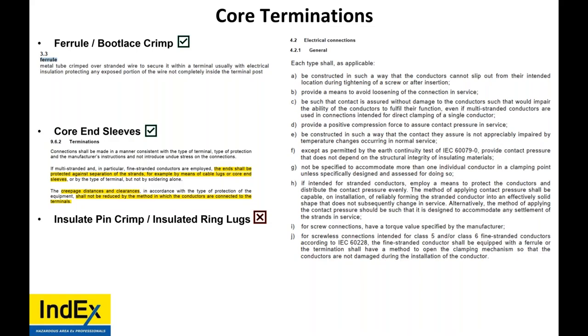14, general requirements for installation. The ends shall be protected against separation of the strands, for example, by means of a cable lug or core end sleeve, or by any other type of terminal. Any other type of terminal. So it doesn't say any other type of termination. All it says is cable lugs and core end sleeves. I think we defined what those are. So when you go into -7 and -15, EXE and N, there's a lot of considerations there, which we're going to go through.